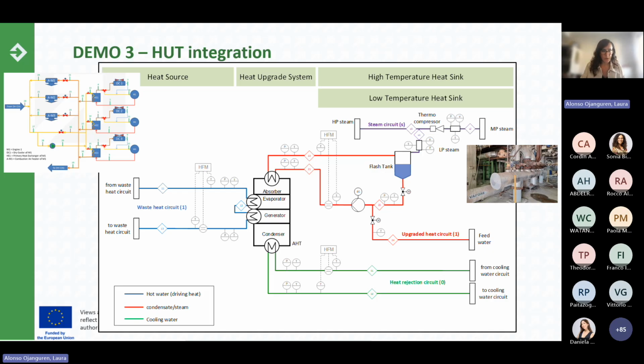Then this water stream goes to the steam generation module. The steam generation module would be more or less this part. Part of the water that comes into the flash tank, only a small part, gets revaporized because it's expanded, and we get the low pressure steam. Then this is mixed with high pressure steam in the thermocompressor, and finally we get the medium pressure steam. As part of the water is revaporized, we need to fill with new water, and this is coming from the feed water line from the deaerator, as in the case of demonstrator number 2, at around 105 degrees.